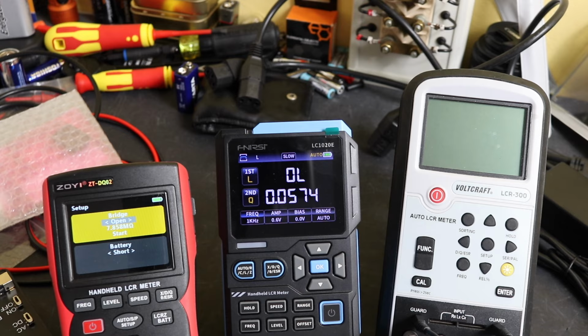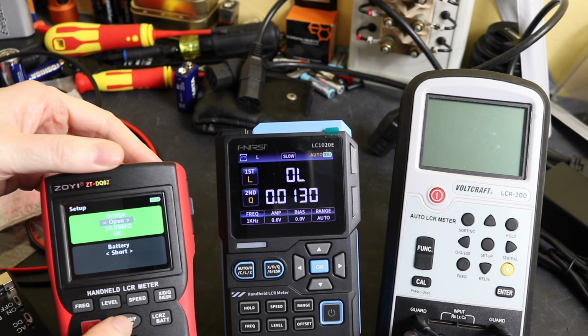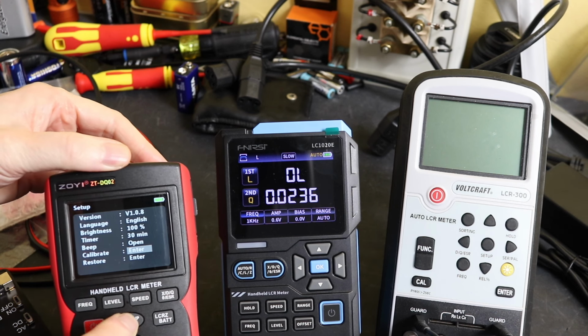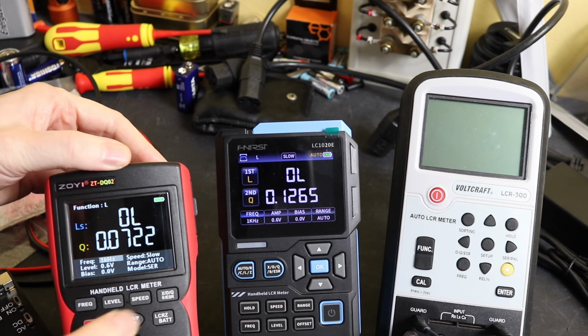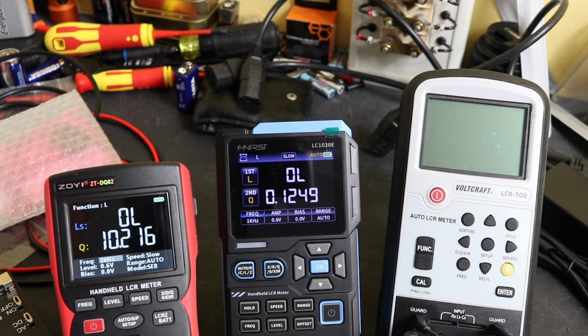Start that off so we can let that run through its calibration, and we'll see if that affects the reading on here. But at this moment in time we are all a little bit puzzled by it all. And we get our little beep and we are all okay. So that's done that. Go backwards again, and we can go on to our 100 microhenry. We're back at 1 kilohertz. 104 at 1 kilohertz, not made an awful lot of difference. We'll up the frequency. We do go up to 106.